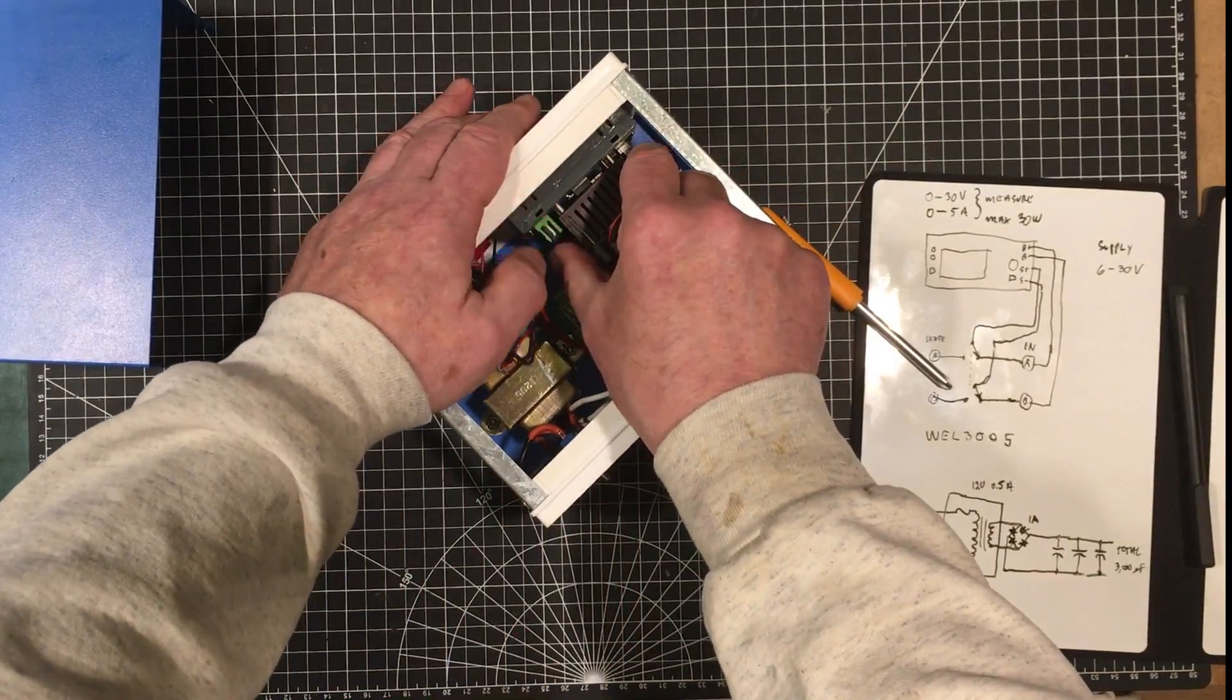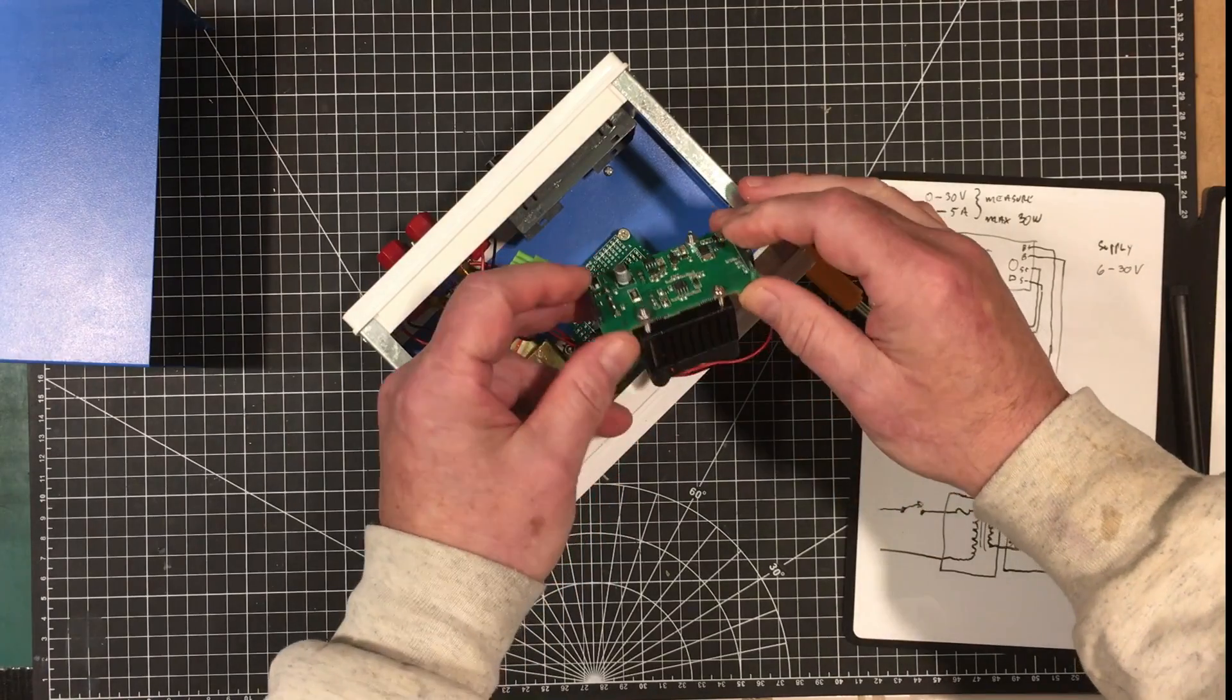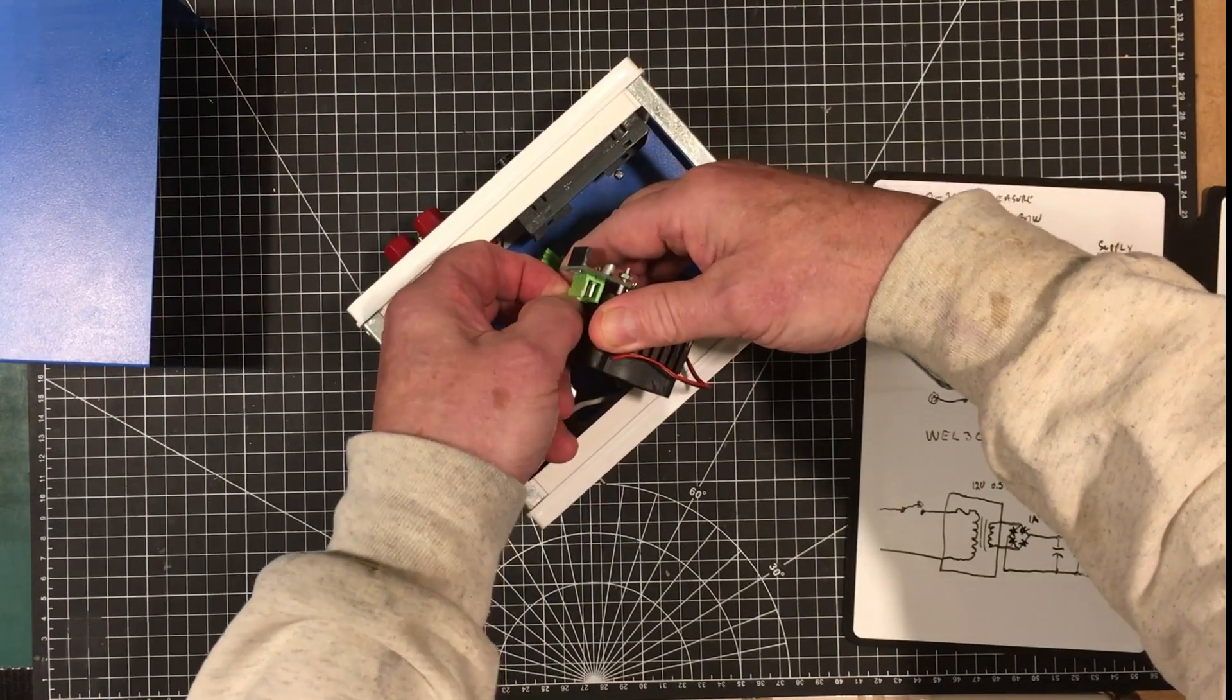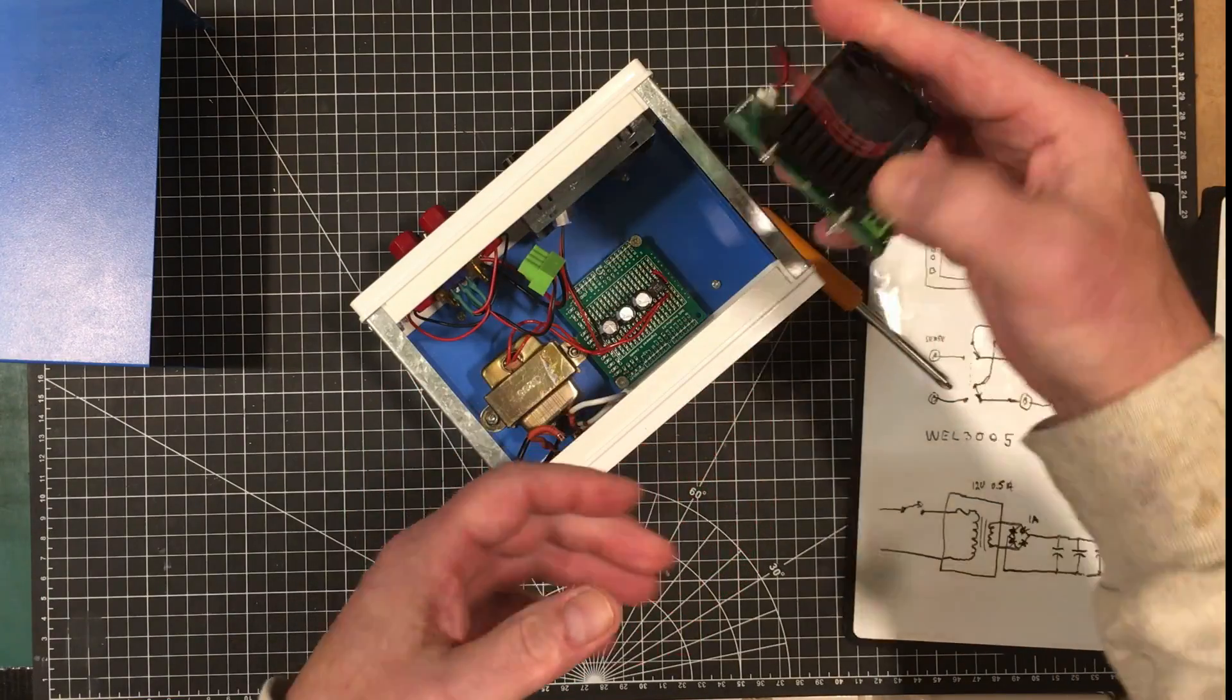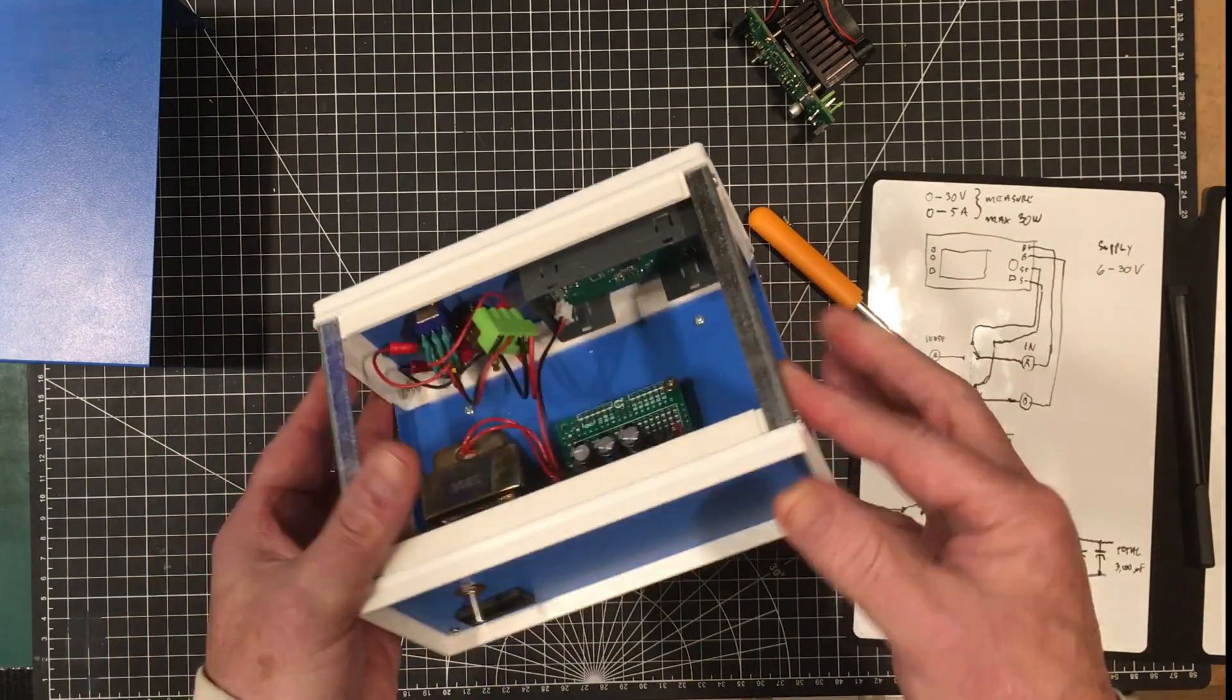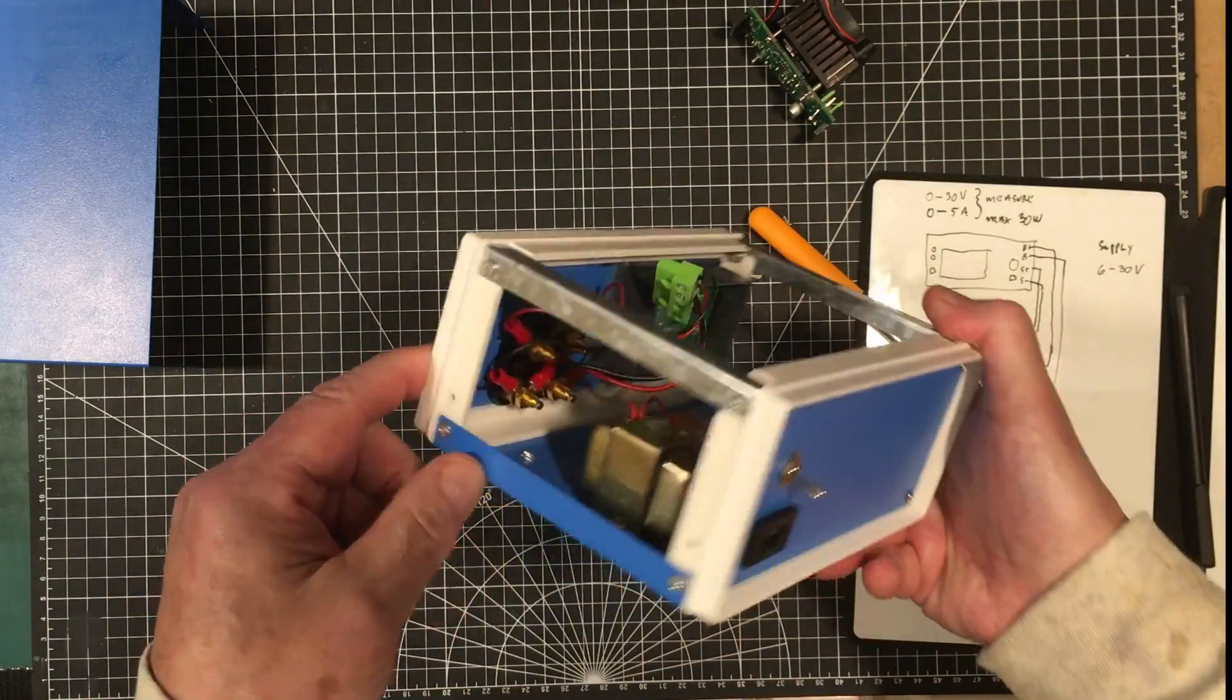That's no problem because the device is built with two boards that have these little header interconnects here, so this can be removed fairly easily for installation of the front part which has got the controls on it. This whole thing can be removed. This is the part that does the dissipation of the power. You can see down in there, there's the control board which does the display and everything. That'll just slide in and clip in place and then you just slide this back into it.